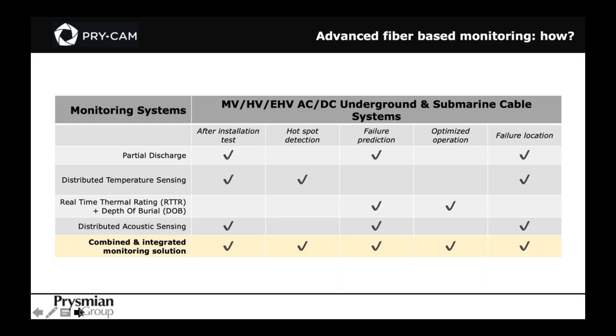Distributed temperature sensing can be used after installation in order to get a temperature baseline of the cable environment. It will allow us to detect hotspots and again locate failures if any.